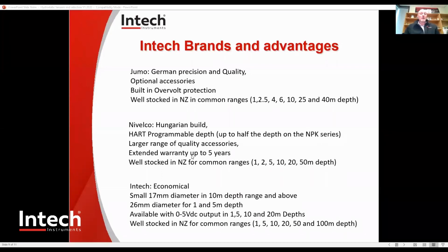It's also available in a 0 to 5 volt output, and in the 10 metre range and above, they have a much smaller diameter, which is great for installation because it means it can go down a smaller pipe and make it easier for installs. The 1 and 5 metre depth models have a 26 millimetre diameter.